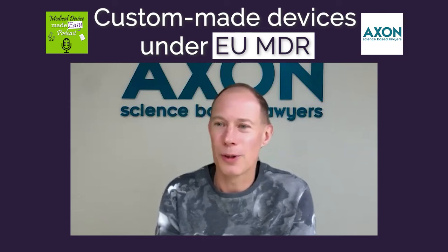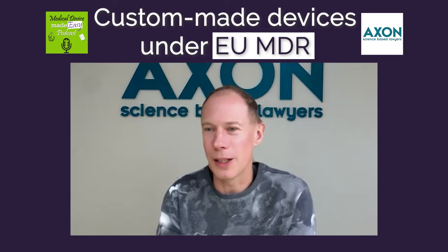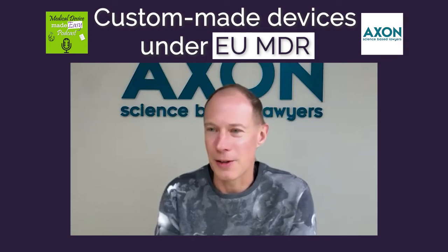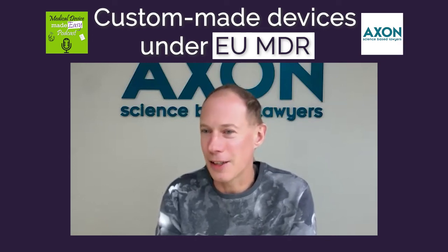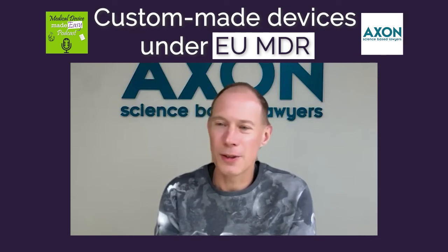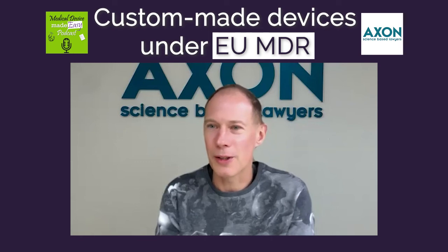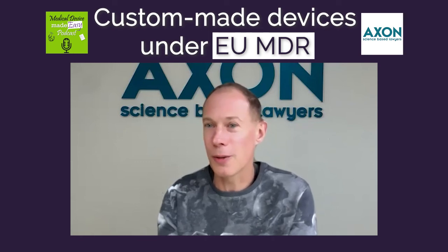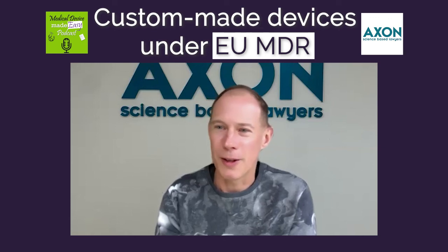If I were a competent authority, this is what I would audit a custom-made devices manufacturer on as a start, because it really shows whether you understand your own production process, whether you are able to function as a company that does this kind of thing. Because I don't care about the Geppetto that makes 2 peg legs a year. That's really not the kind of risk I would like to regulate as a regulator.